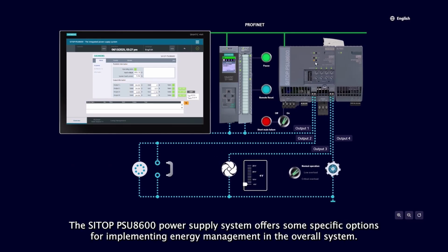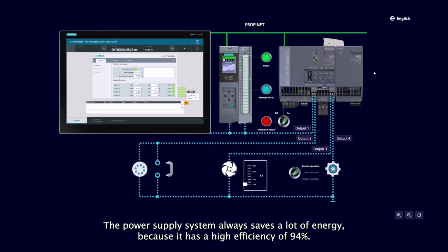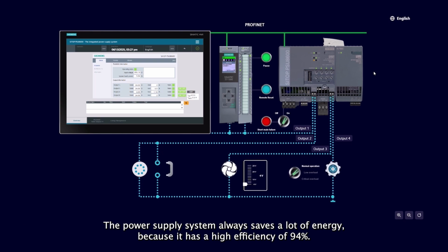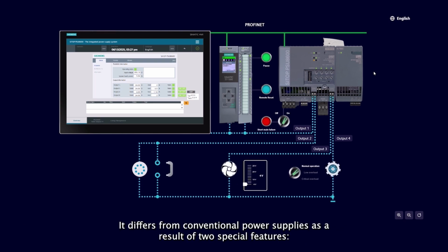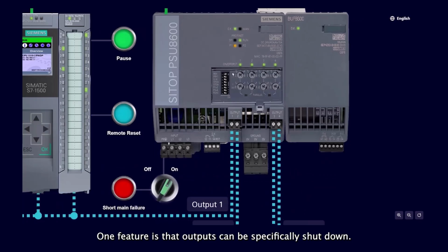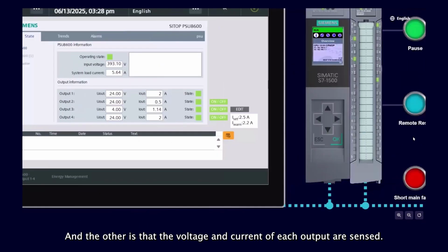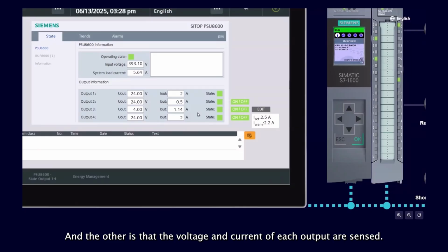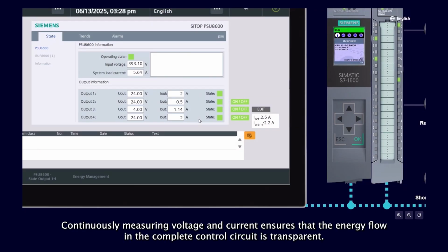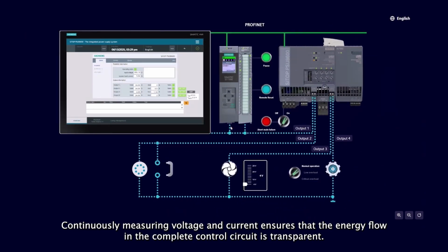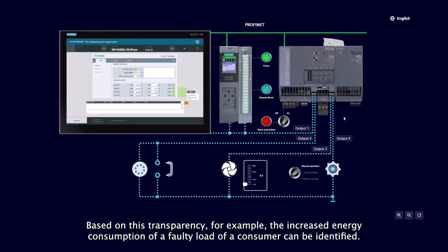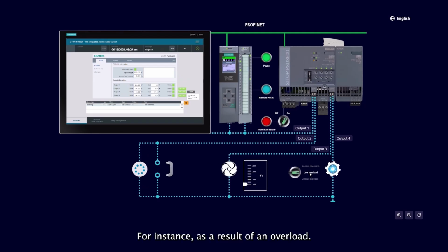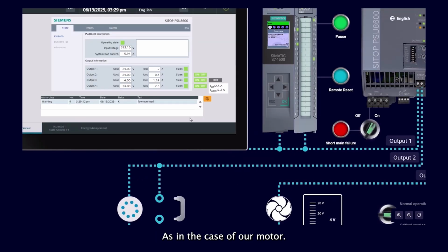The SITOP PSU8600 power supply system offers some specific options for implementing energy management in the overall system. The power supply system always saves a lot of energy because it has a high efficiency of 94%. It differs from conventional power supplies as a result of two special features. One feature is that outputs can be specifically shut down, and the other is that the voltage and current of each output are sensed. Continuously measuring voltage and current ensures that the energy flow in the complete control circuit is transparent. Based on this transparency, for example, the increased energy consumption of a faulty load or consumer can be identified, for instance, as a result of an overload, as in the case of our motor.